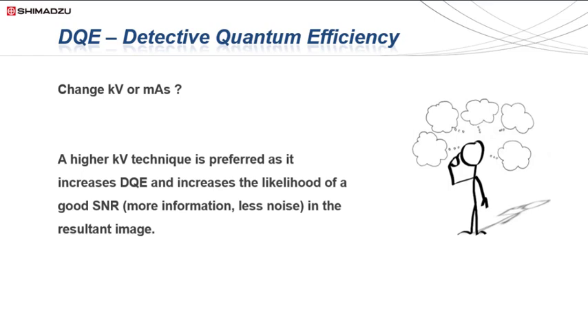So what do we change — KV or MAS? It is recommended by the manufacturer of most flat panel detectors to preferentially apply a higher KV technique, as it increases the detective quantum efficiency — in layman's terms, the readability of the detector — to optimise signal-to-noise in the resultant image. You will notice that a lot of the programmed exposures in your unit have a very short MAS. This allows for reduced absorbed dose in patients while allowing the digital detectors to still maintain a level of detector scintillation.